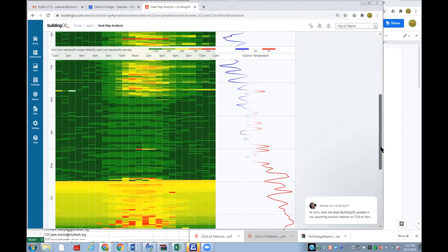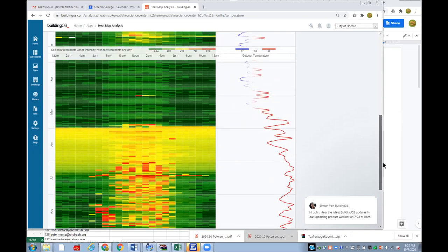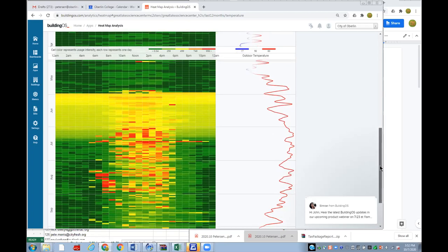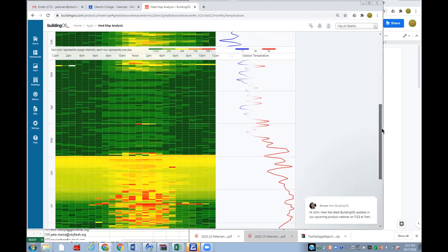Yeah. This is interesting. In June, they must irrigate the landscape. I have no other explanation for why you'd get this yellow, or they had a low-level leak the entire time, because they're using 411 gallons of water. This is really interesting. This is what I'm talking about. This is where the detective work comes in. I don't know what's going on there, something funky. That's really funky, that pattern. There's something wrong. And it fades in. Notice it's fading in. So it seems almost like they're tuning things down. That's what makes me think maybe it's irrigation.